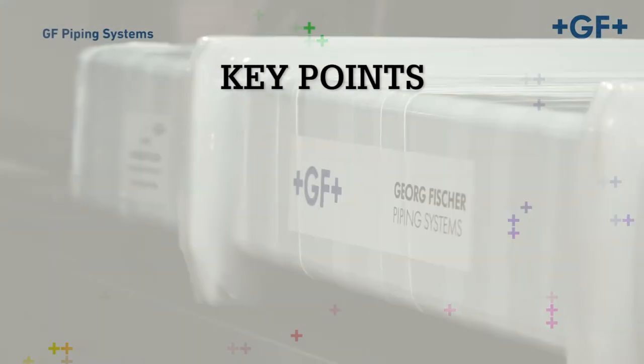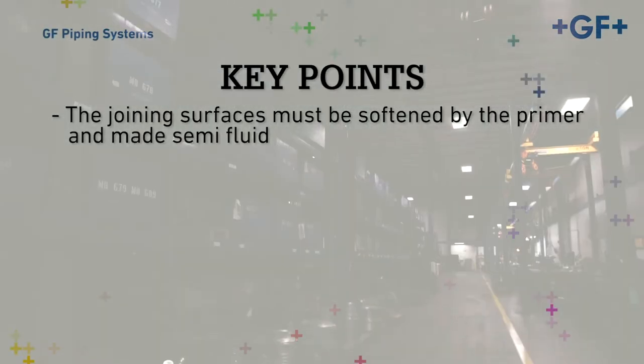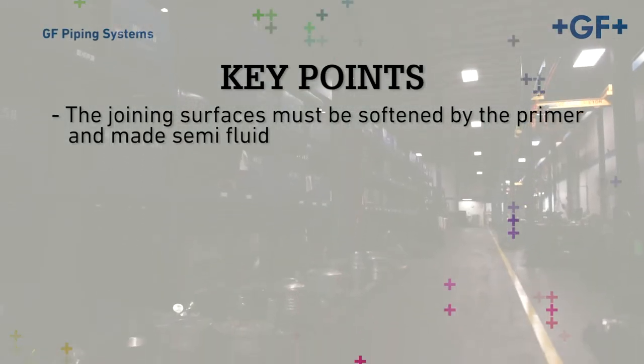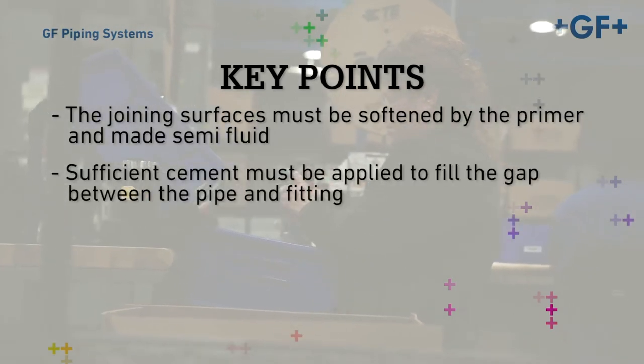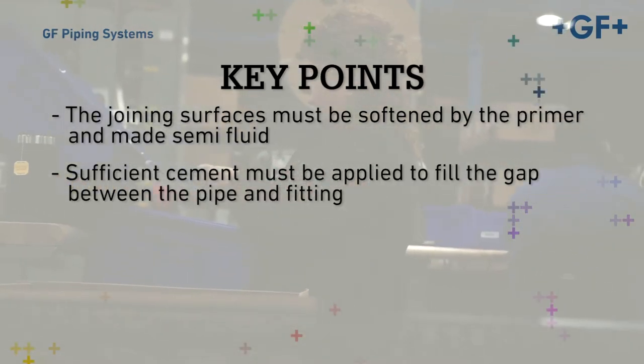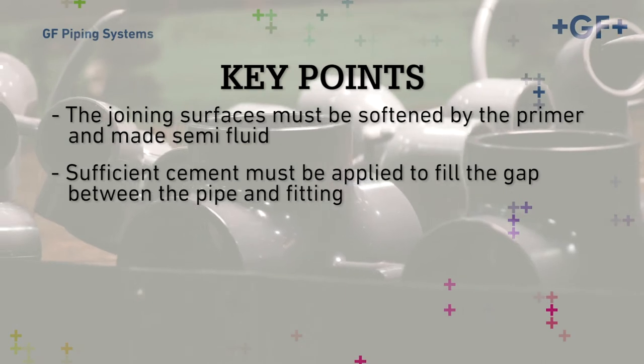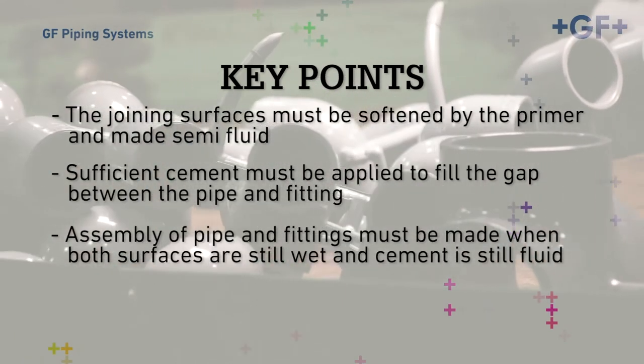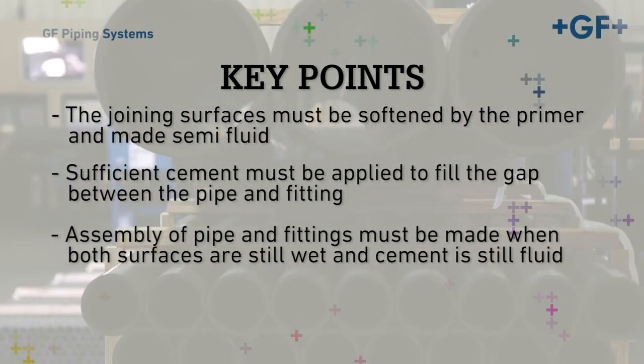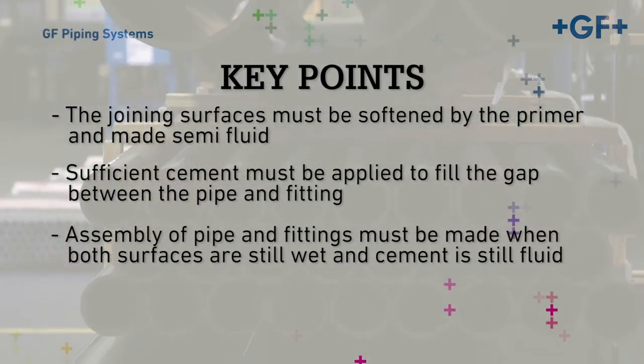Key points to remember are as follows. The joining surfaces must be amply softened by the primer and made semi-fluid. Sufficient solvent cement must be applied to fill the gap between the pipe and fittings. Assembly of the pipe and fitting must be made when both surfaces are still wet and solvent cement is still fluid.